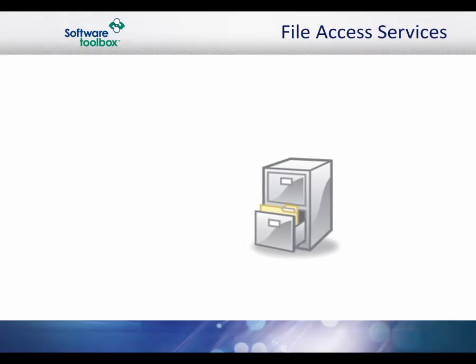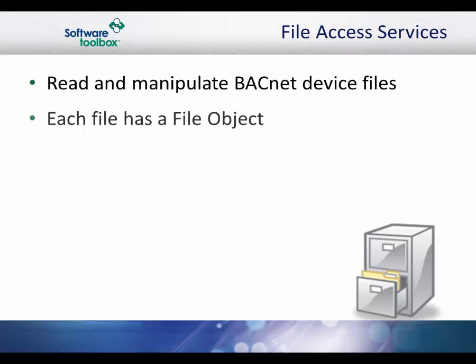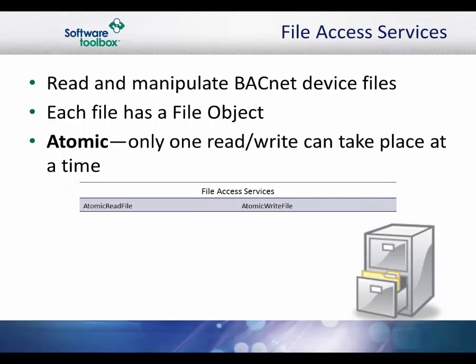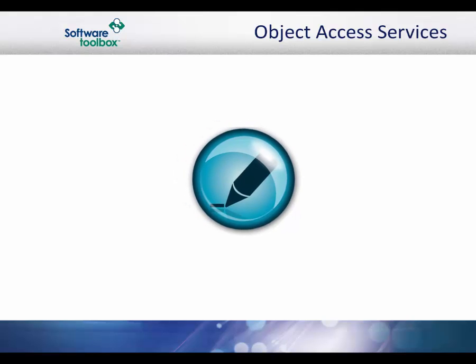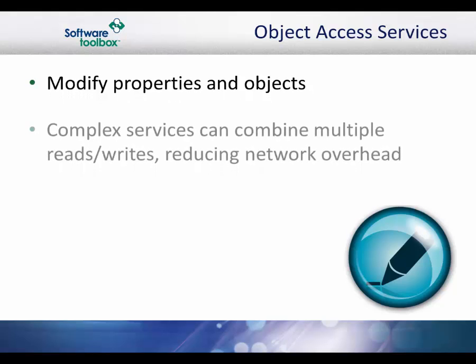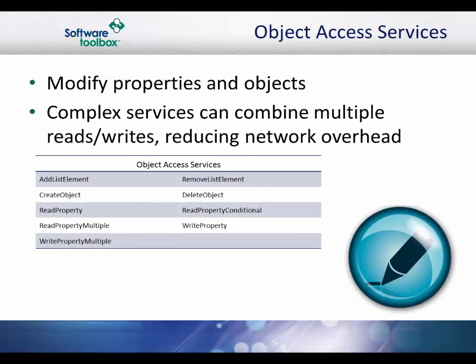File access services are used to read and manipulate files in a BACnet device. In BACnet, files represent grouped data bytes of arbitrary length and meaning — they do not necessarily relate to any kind of mass storage device. Every BACnet accessible file has a file object associated with it. The word atomic in the service name merely means that only one read or write operation can take place at a time. Object access services provide the means to read, modify, and write properties, and to add and delete objects. Multiple services are provided for reading and writing properties. The purpose of the more complex services is to combine as many reads or writes to properties of objects within a BACnet device into a single message, thus reducing network overhead.